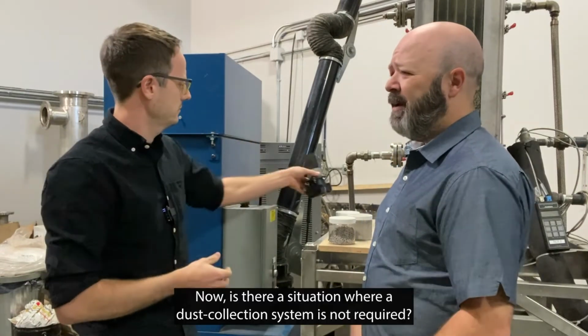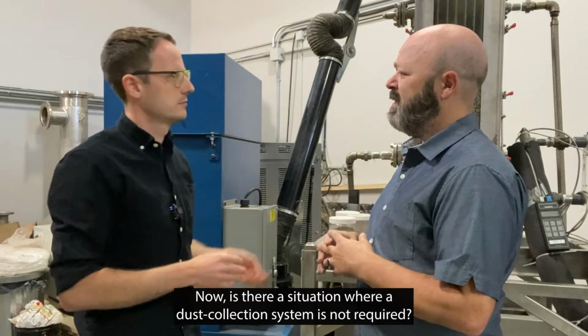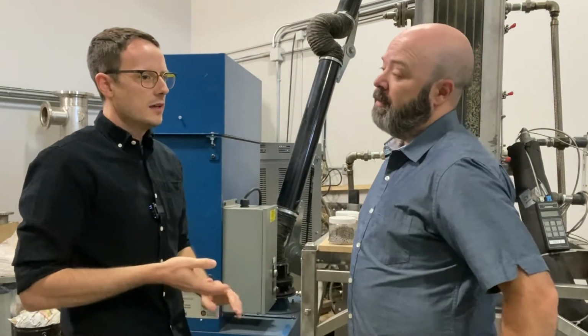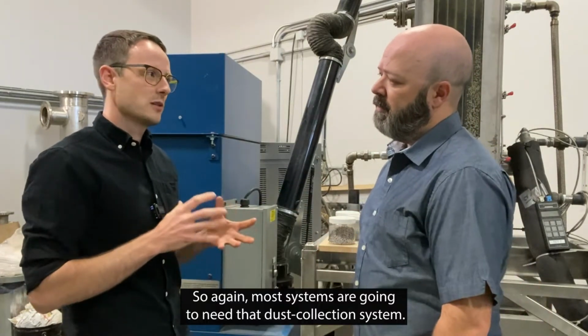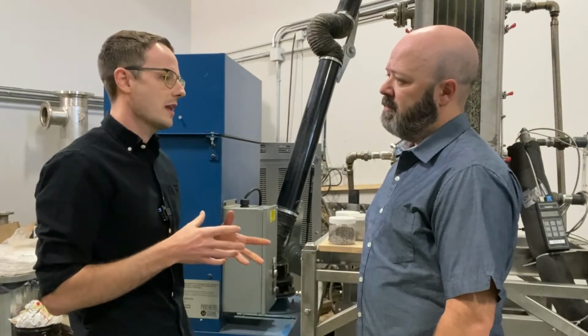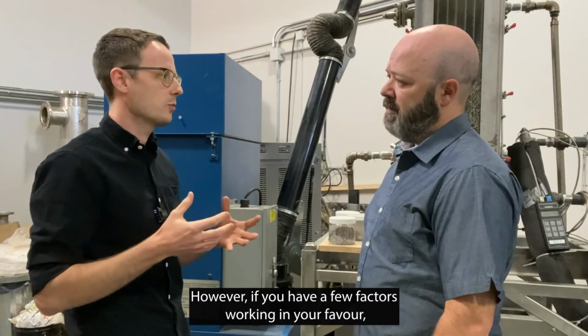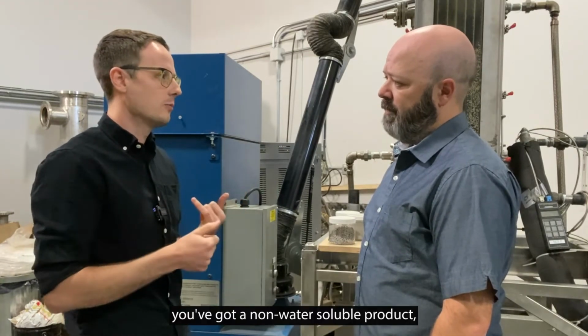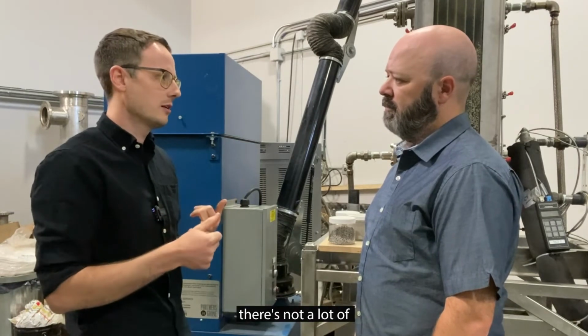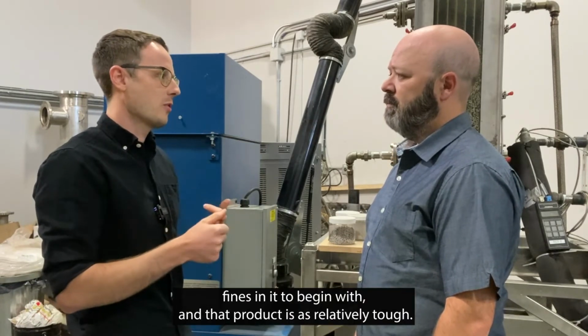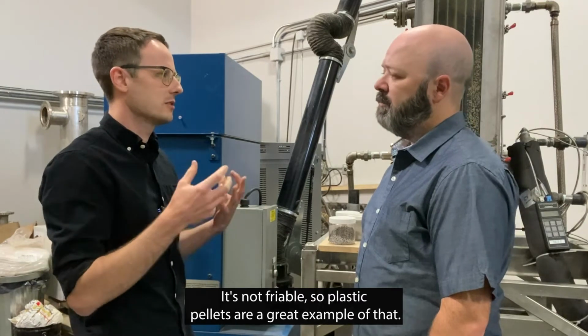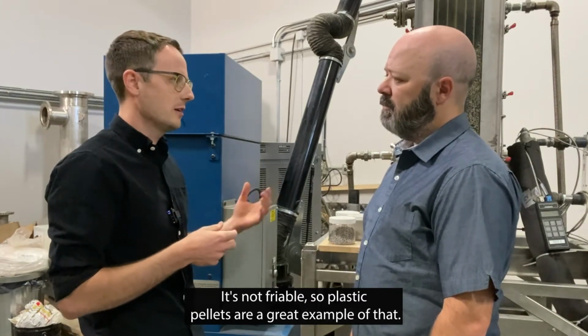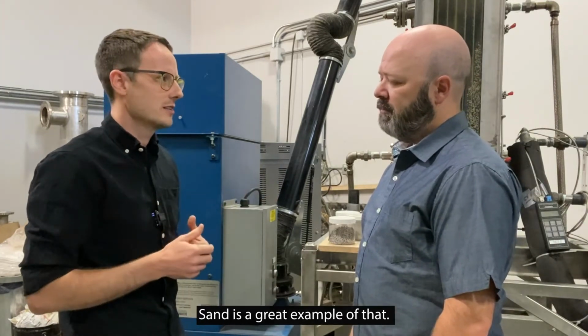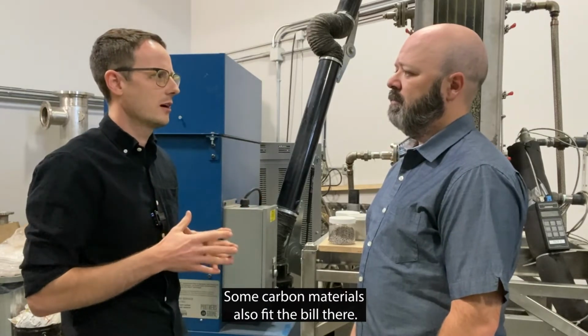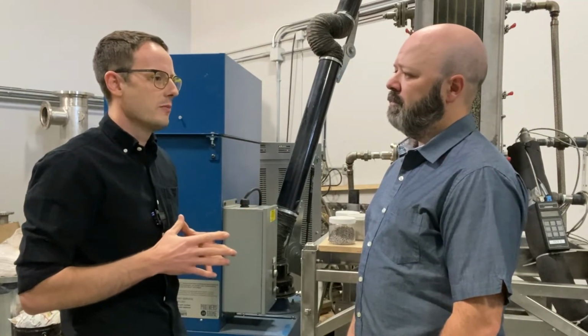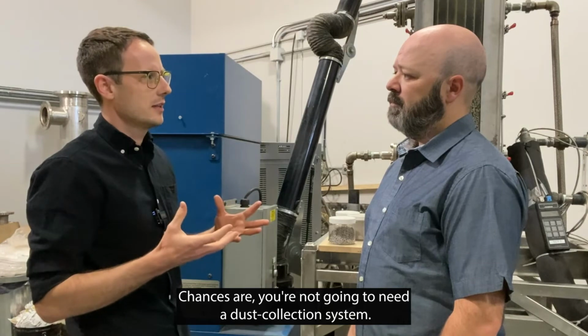Awesome. Now, is there a situation where a dust collection system is not required? Yeah, so again, most systems are going to need that dust collection system. However, if you have a few factors working in your favor, you've got a non-water soluble product, there's not a lot of fines in it to begin with, and that product is relatively tough. It's not friable. So plastic pellets are a great example of that. Sand is a great example of that. Some carbon materials also fit the bill there. Chances are you're not going to need a dust collection system.